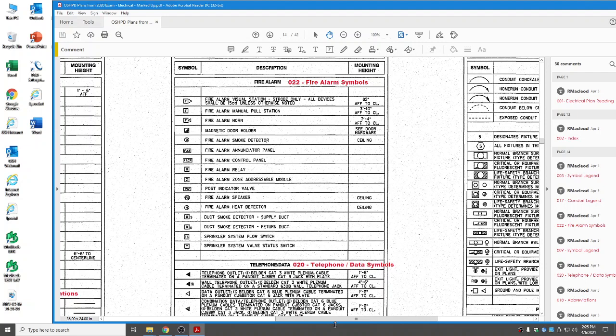of the visual device. The next item is just an F and a square for a fire alarm manual pull station. Typically you'll find these at your exits or by stairways in multi-story buildings. Next item is a fire alarm horn. You notice it kind of looks like a little horn blowing out. There's also a chime symbol that you'll see that isn't really on this particular set of drawings here. We don't use horns in hospitals, except maybe in very large basements or mechanical rooms where there's a lot of noise, because we need to have chime sounding devices anywhere that the public or the patients are being seen. So typically we're going to see fire alarm chimes, not fire alarm horns, and that's at 7'4" above floor finish to the center line of the device.